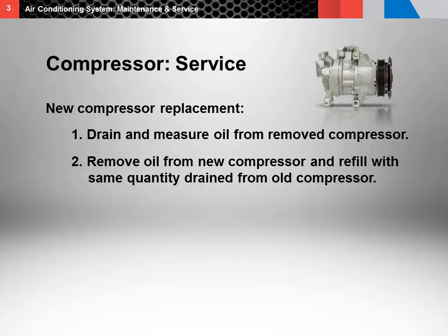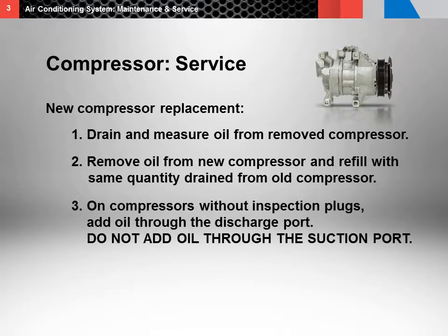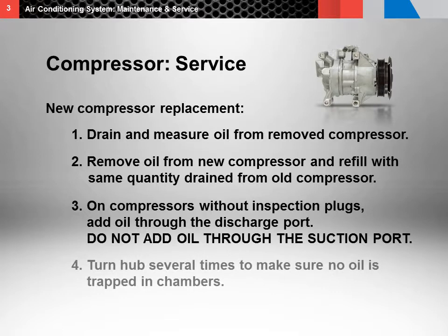If there are no inspection plugs, add oil to the compressor through the discharge port. Do not add oil through the suction port. Turn the compressor hub several times by hand to make sure no oil is trapped in the compressor chambers.